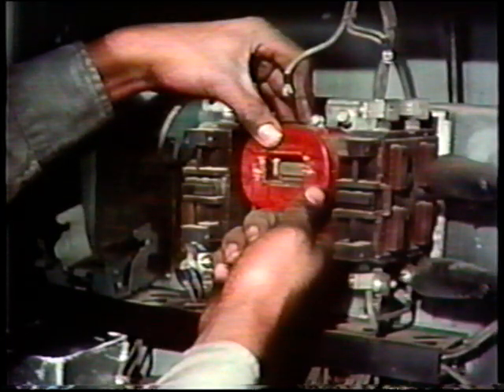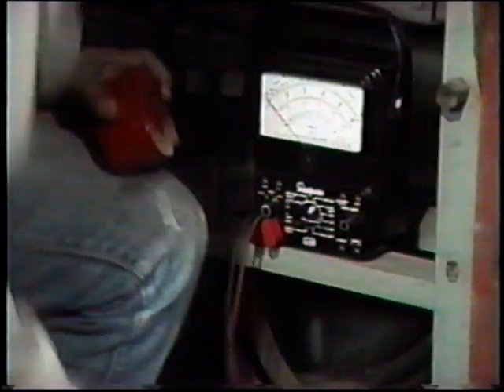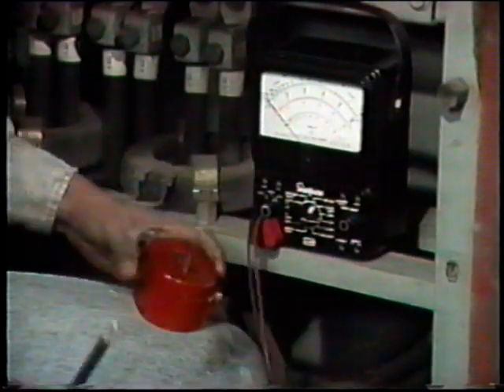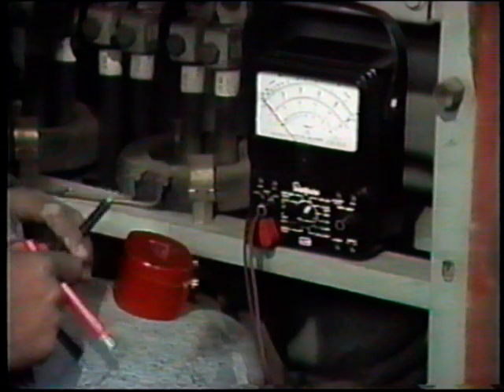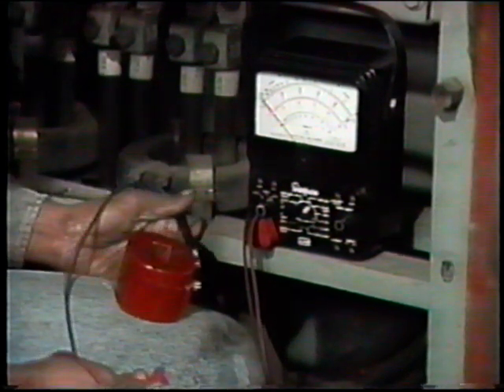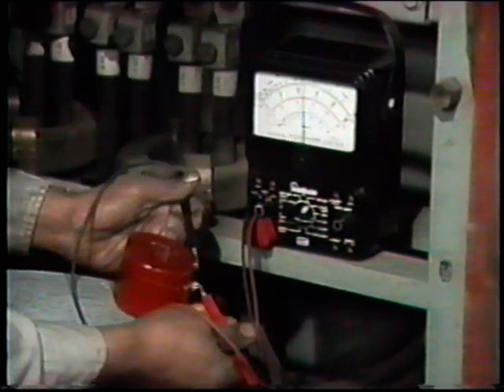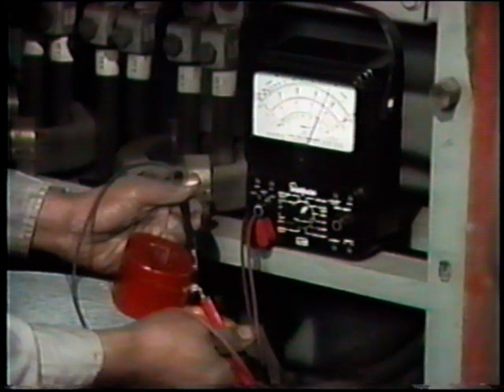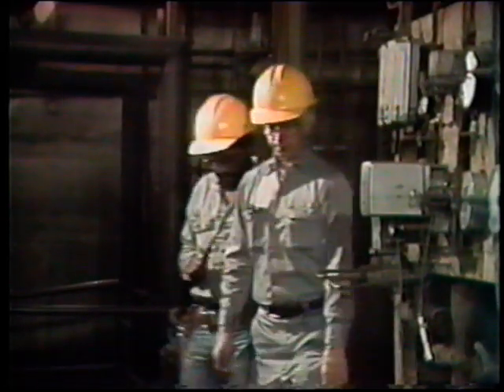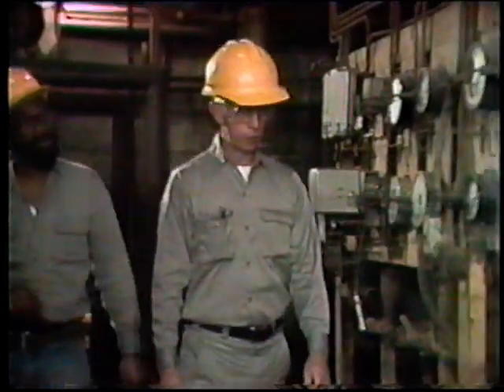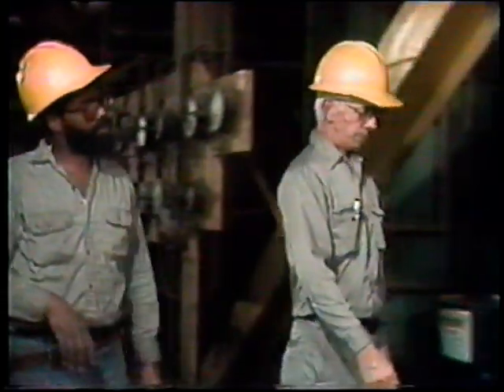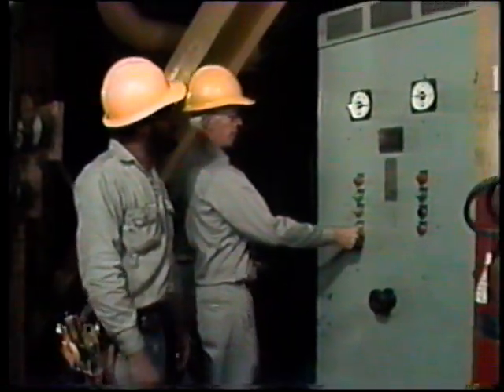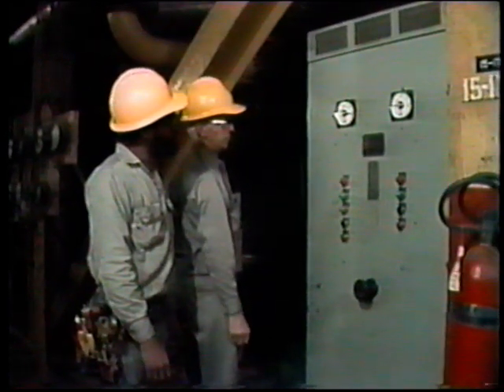Once it has been determined that a component does have a problem, then the bad component must be replaced by a new component of the same size and rating as the old one. Before installing a new component, it's a good idea to test it and make sure that it's good. After correcting a controller problem, the tags can be removed and the controller can be energized. Then a test run of the equipment should be made to make sure that there aren't any other problems.